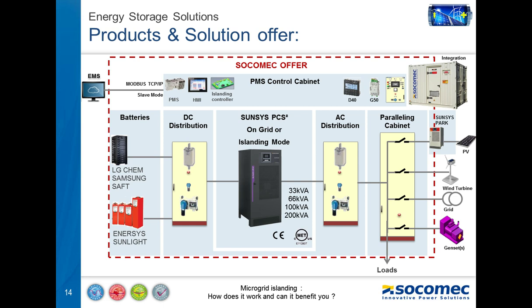Okay, so concerning Socomec's offer, we are offering a turnkey solution with batteries that can be lithium-ion or lead acid, with DC and AC distribution cabinets, and paralleling cabinets in order to parallel all the sources that can be PV, wind, grid, gensets, hydro, whatever the application has. We offer also the SUNSYS Park, which are the PV inverters, the SUNSYS PCS Square, that are our bidirectional power converters that can be on-grid only or on and off-grid, so with the islanding mode option, and the PMS control cabinet.